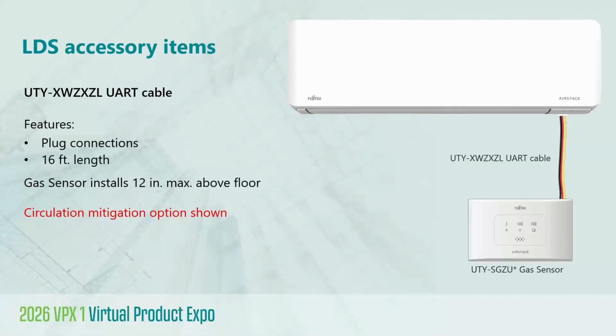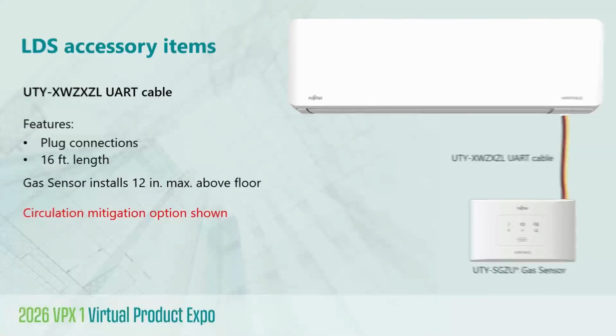It's also important to remember that the gas sensor must be installed no more than 12 inches above the floor level. So that's why, again, you want to factor the 16 feet. So again, as an important reminder, if you are installing a ducted or floor-mounted unit, you guessed it, you will not need the LDS accessory items that you see here.